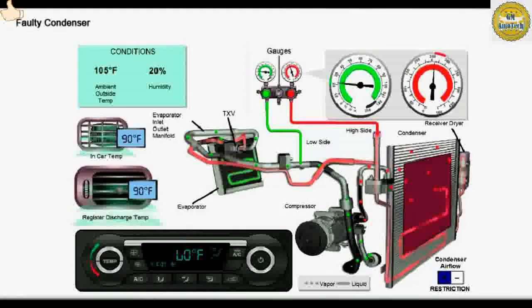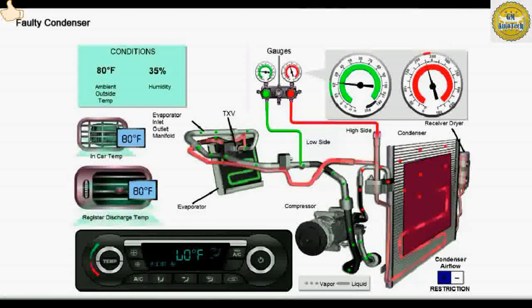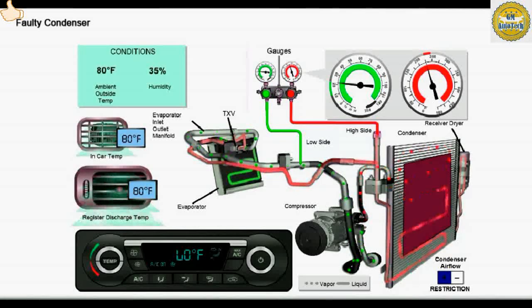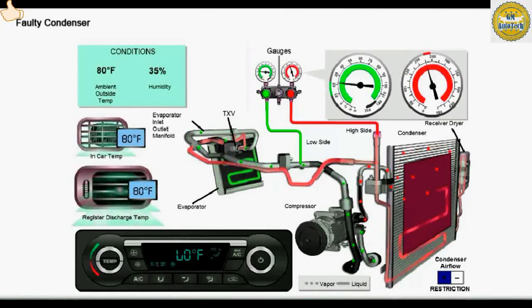A restricted condenser will cause the high side pressure to be high and the low side pressure to be low. Condenser failures are usually caused by internal restrictions.